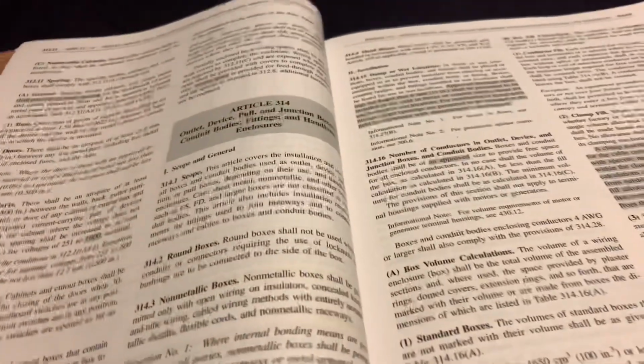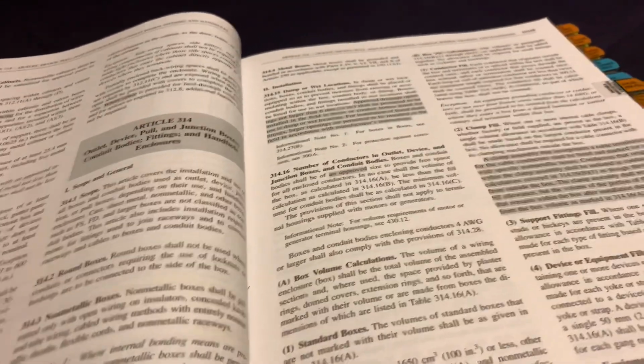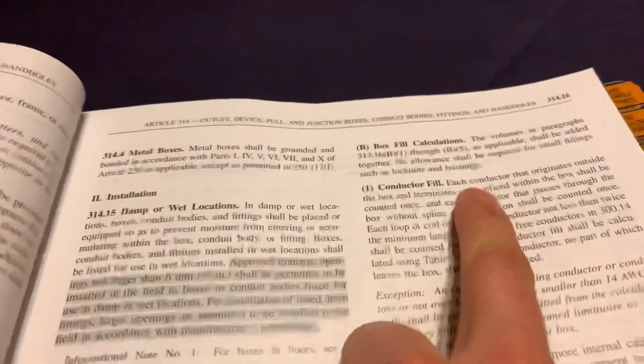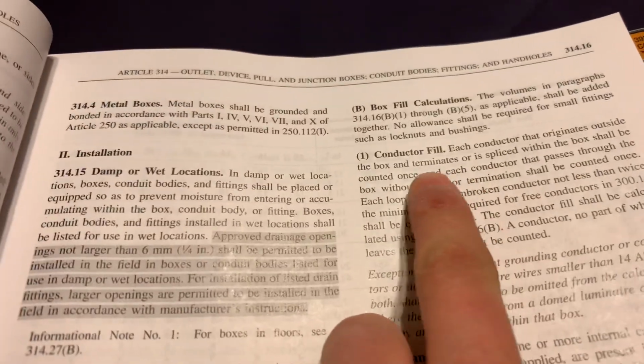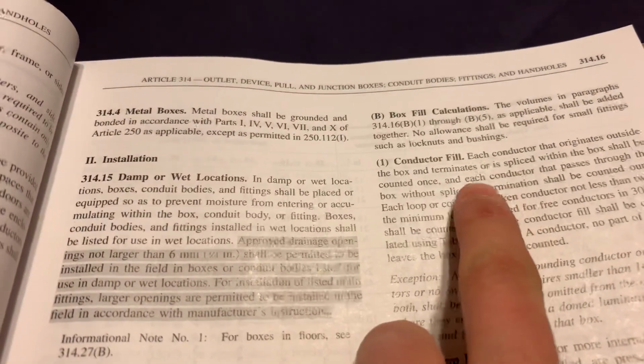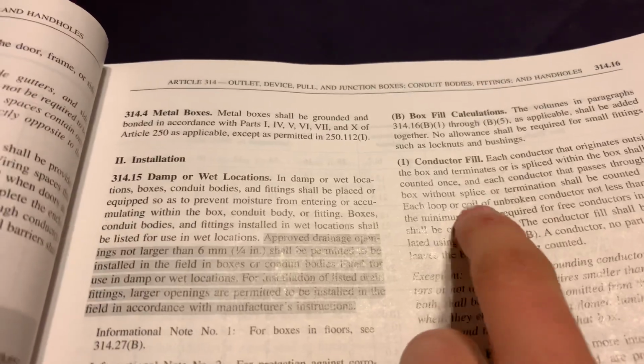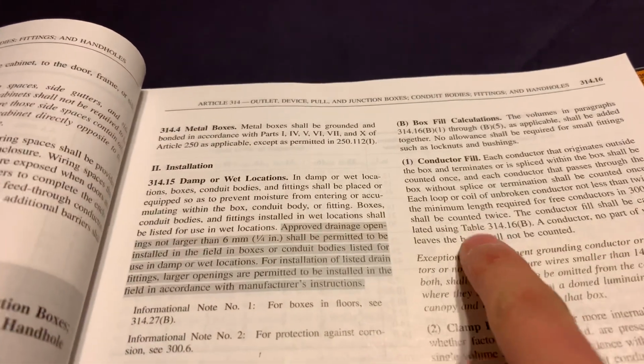And then the other thing I was talking about, the conductor fill right here. So each conductor that originates outside the box that terminates or is spliced within the box shall be counted once. And then if wires pass through, it's counted once.